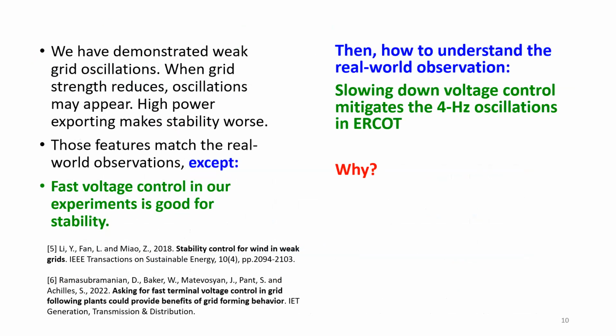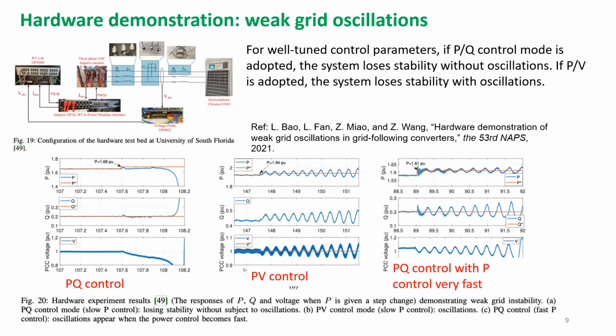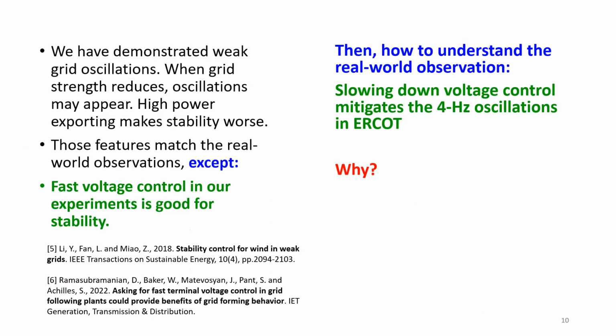However, there's one exception: the fast voltage control in previous cases all behaved better, making the system good. For example, in the PV control case, if we make the voltage controller faster, the oscillation goes away. This is very different from real world observation, because in the real world, fast control is bad, so they tune down the controller. I confirmed with ERCOT people and they told me, yeah, that's what we do.